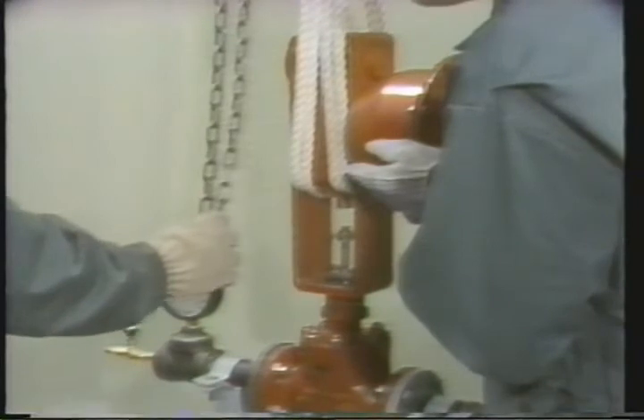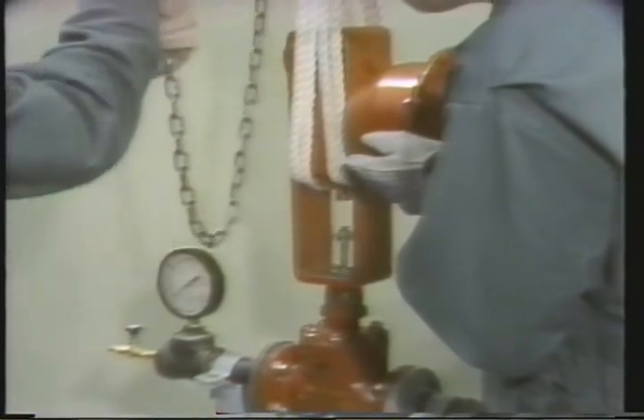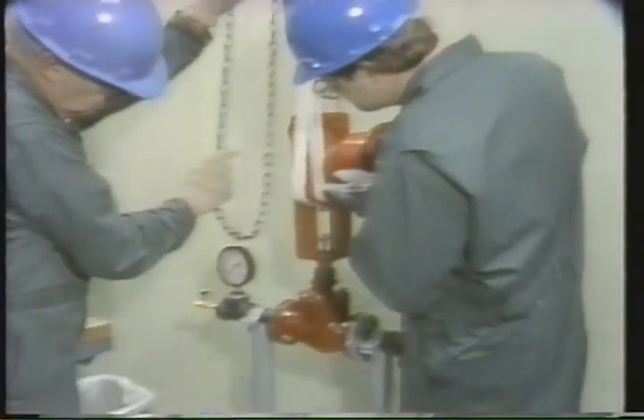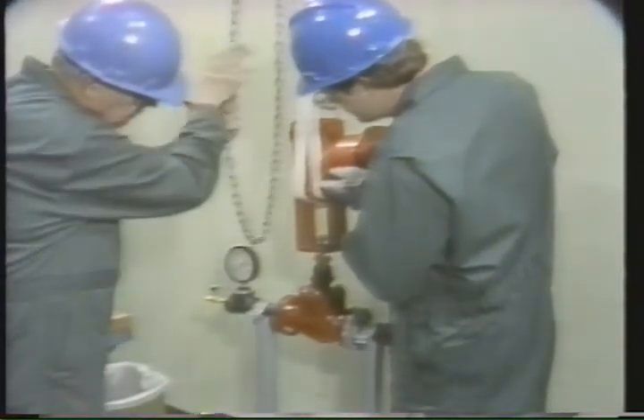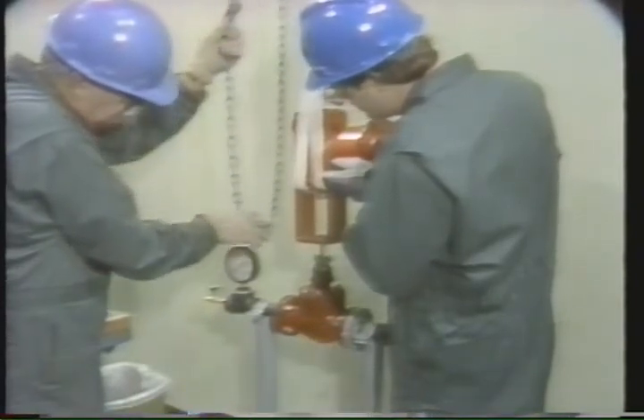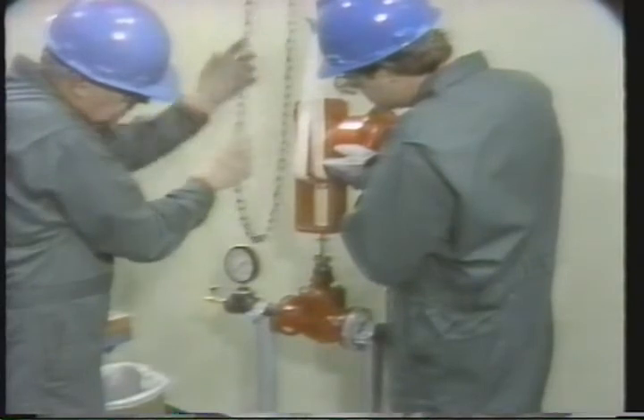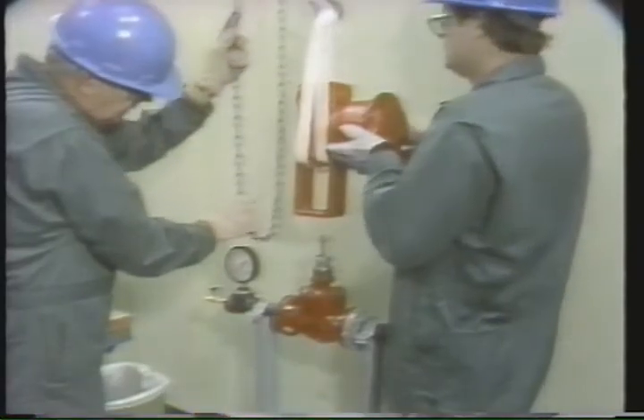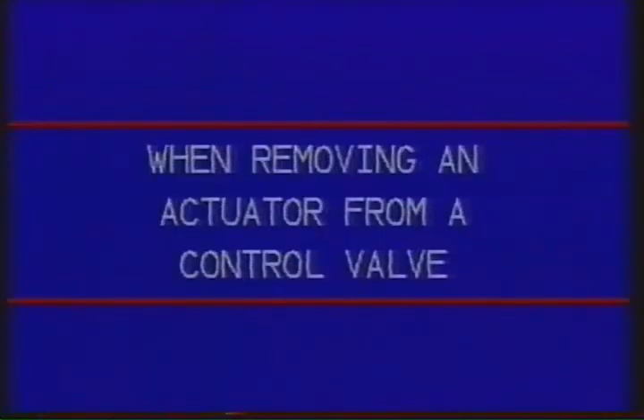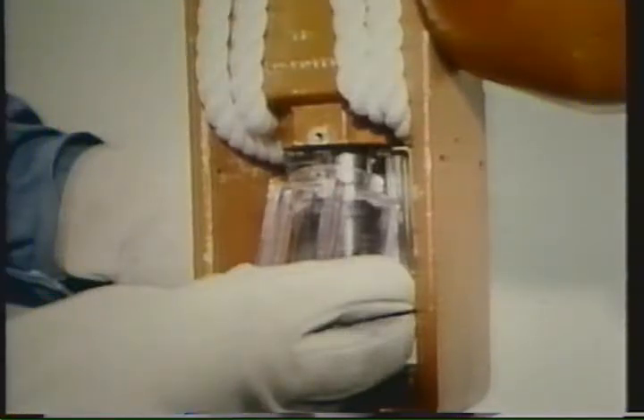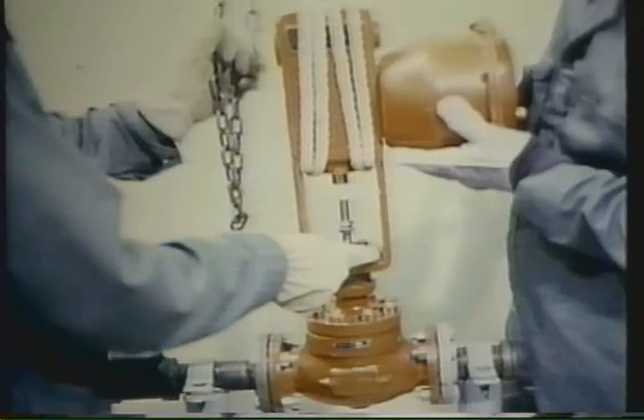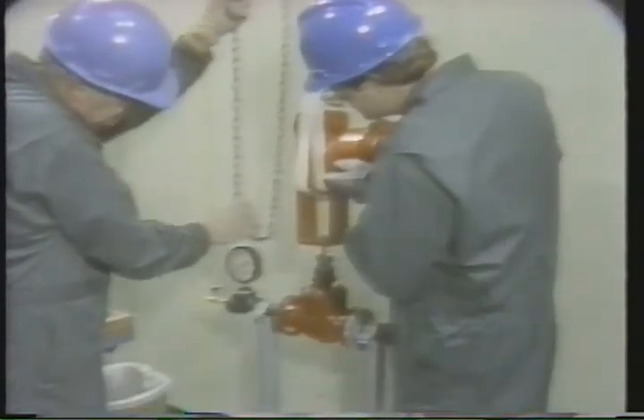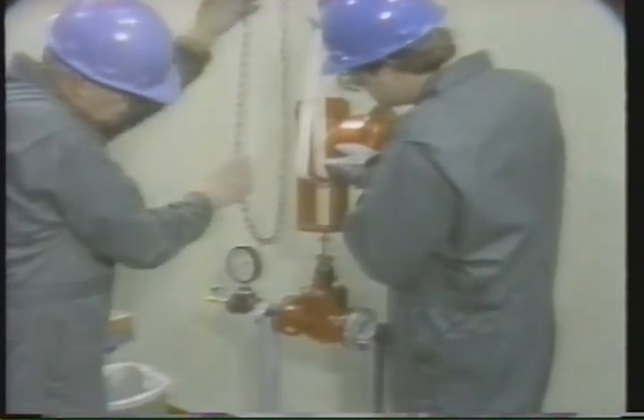This allows the technician to keep control of the hoist. As the technician continues hoisting to completely lift the actuator off the valve, he takes care to keep the movement steady and straight. It's important that the actuator clears the valve stem without damaging the stem. Scoring or other damage to the stem could affect the operation of the valve. Remember, some actuators have accessories that must be removed before hoisting the actuator off the control valve. Follow your facility's safety procedures for hoisting and lifting, and make sure that the actuator is lifted straight over the stem to prevent damage to the stem.